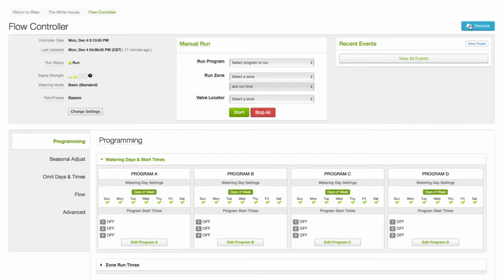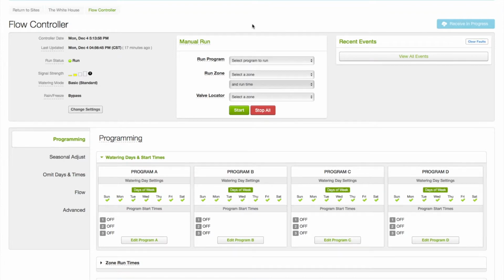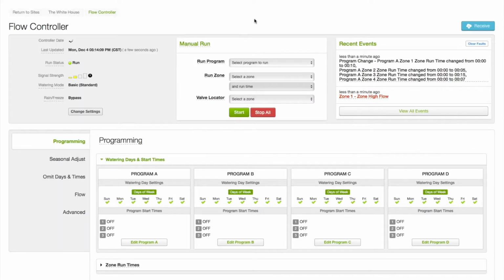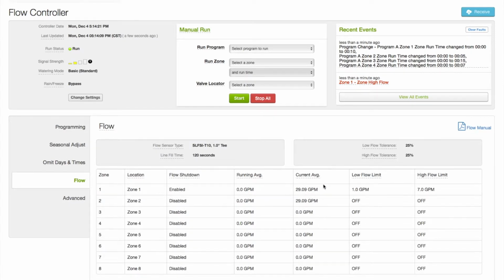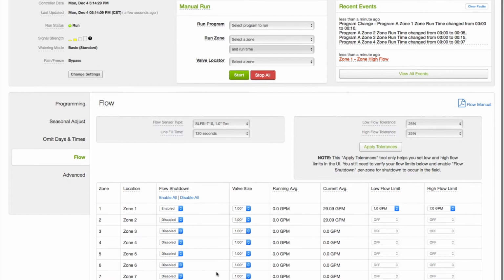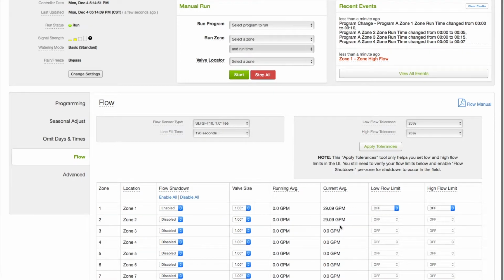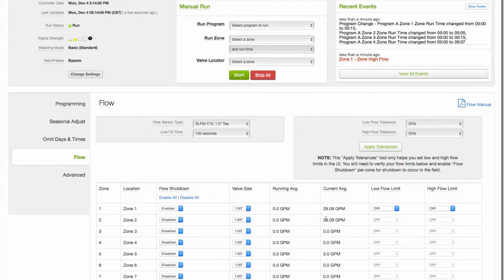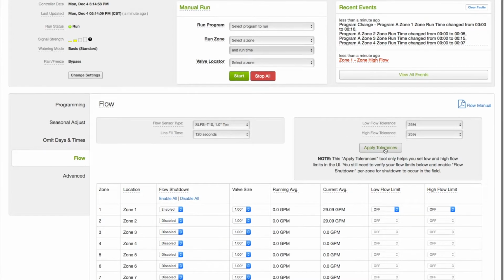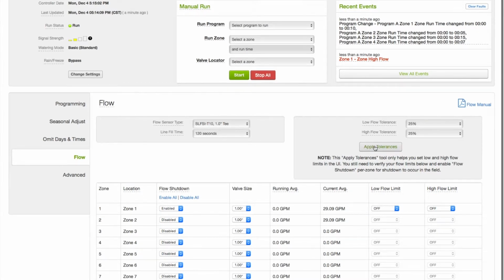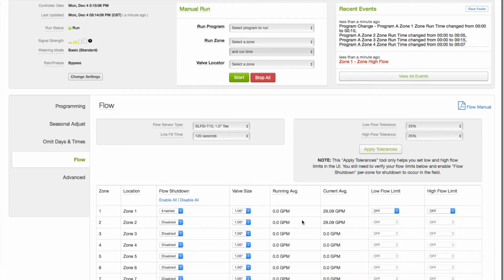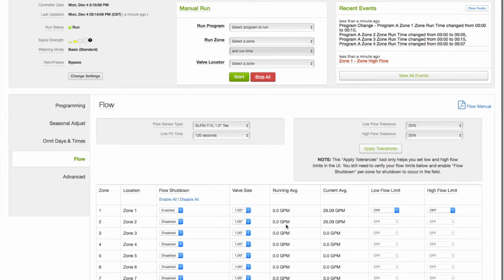Okay, so now we're going to take a receive command and receive the information from the controller via the Smartlink modem into the Smartlink cloud-based software. And now we'll check for flow data, which we see that we have here for zones 1 and 2. So now we want to edit flow settings. And now we have our flow settings come back. So what we'll want to do is we'll need this to run for a few days to populate this running average column before we can apply the tolerances. The tolerances will apply to the running average after there's enough data and time passed that this column populates.